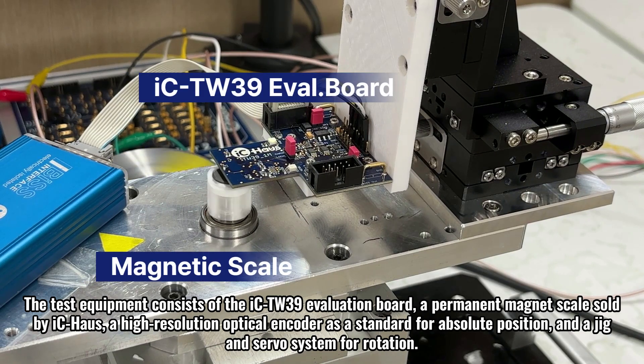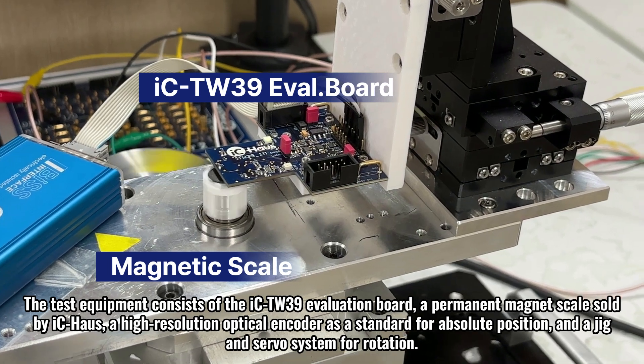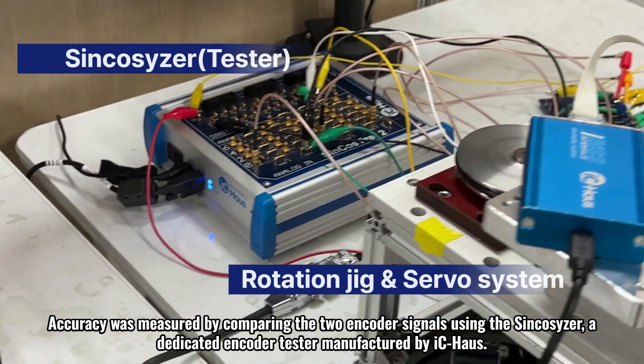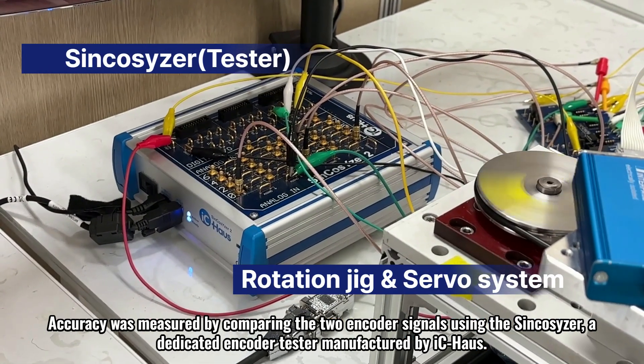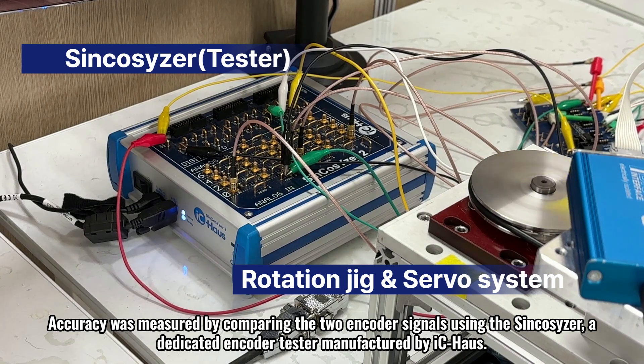The test equipment consists of the IC-TW39 evaluation board, a permanent magnet scale sold by iC-Haus, a high-resolution optical encoder as a standard for absolute position, and a jig and servo system for rotation. Accuracy was measured by comparing the two encoder signals using the Sincosyzer, a dedicated encoder tester manufactured by iC-Haus.